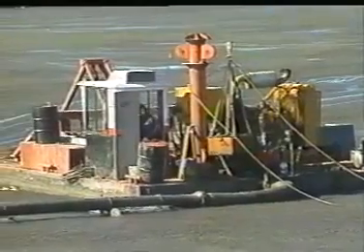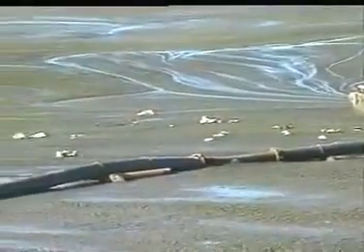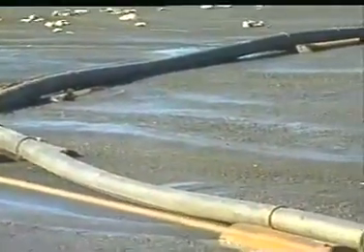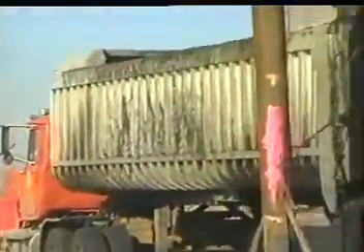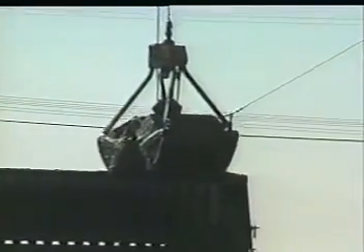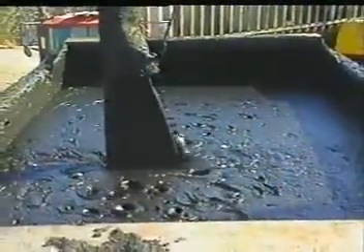In a full season's pumping under contract with a major metropolitan wastewater treatment agency, EDDY 1 successfully pumped 13.8% dewatered sludge at an average rate of 2,800 gallons per minute, with discharge distances ranging up to 1,380 lineal feet. In one 8-hour shift, the EDDY 1 dredge registered nearly 1.4 million gallons of sludge. Transport trucks of 20 to 29 cubic yards, traditionally loaded by dragline in 10 to 14 minutes, were filled by the eddy pump in 1 to 3 minutes, with no spillage or overflow.